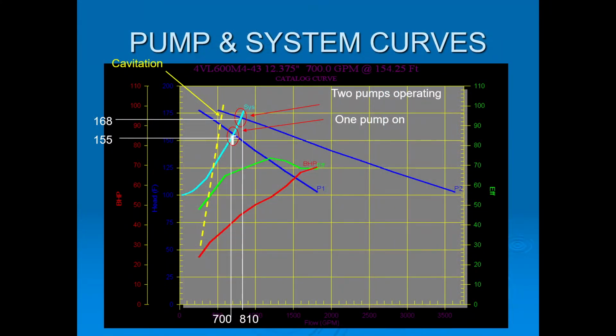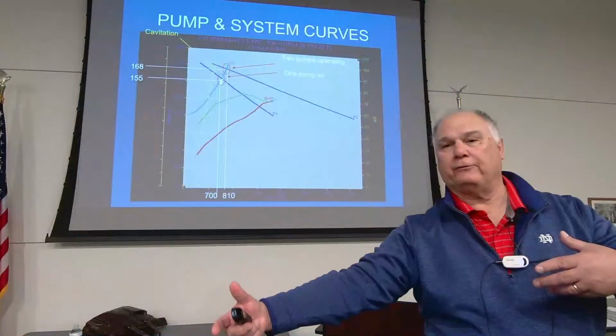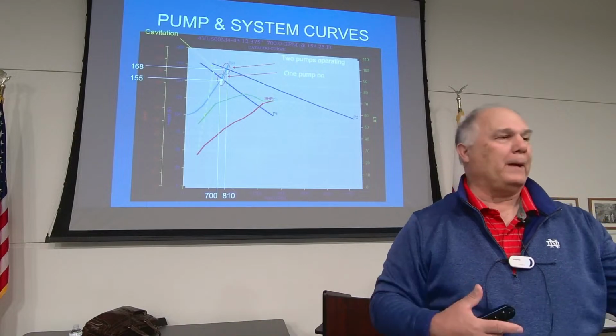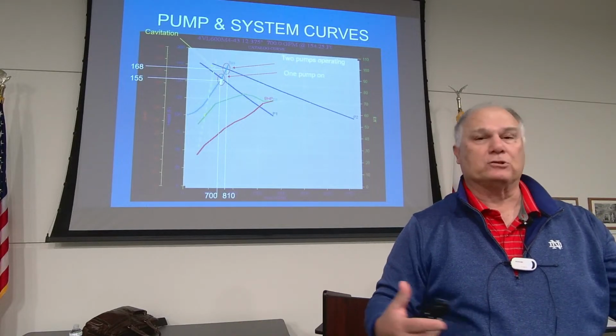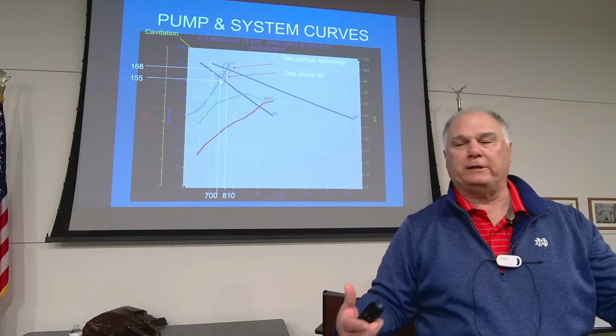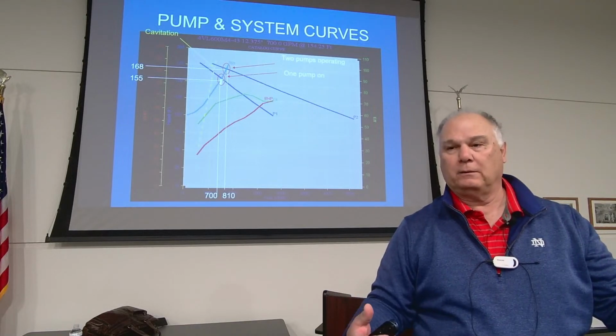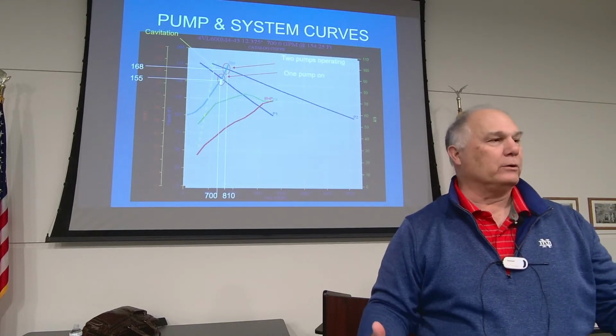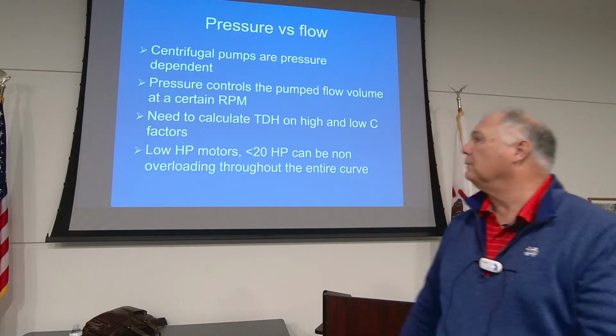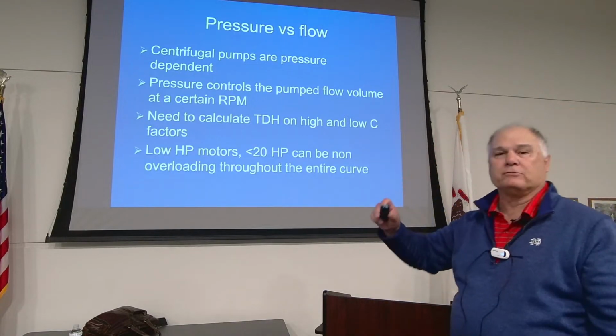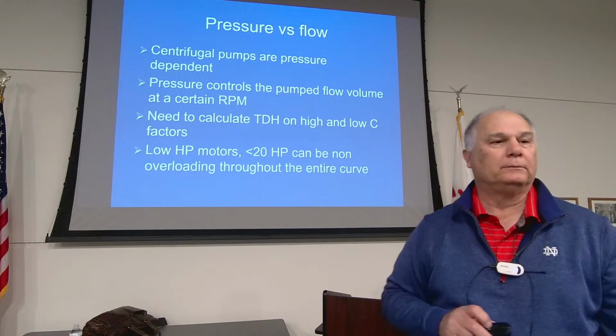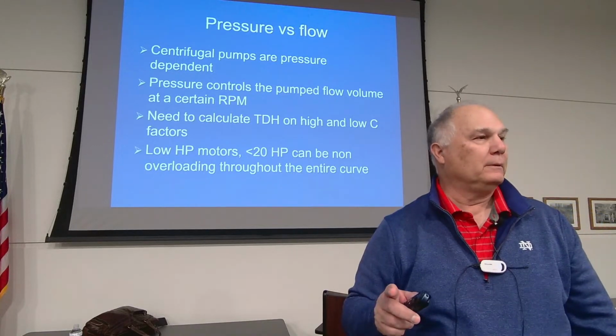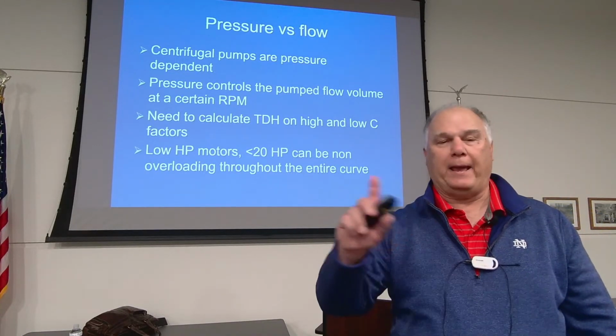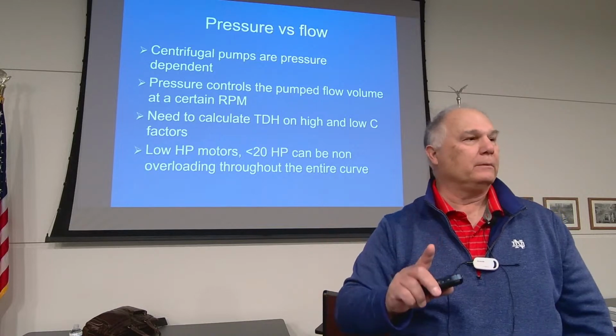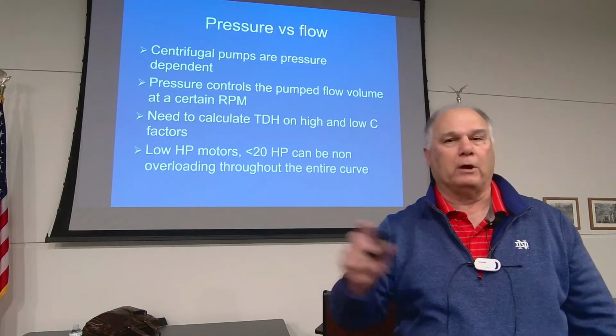But that same impeller will do anywhere from 1,500 gallons a minute all the way back to 700 gallons a minute, based on the friction or pressure it needs to generate. And that's how you understand pump curves. Pump curves are always based on pressure. We talk about volume, but we have to talk about volume and pressure at the same time to really understand what's going on with that station.